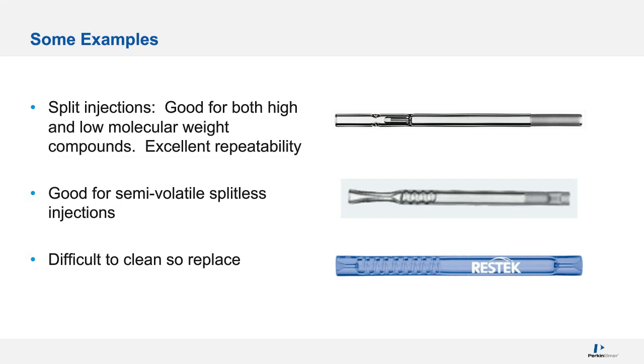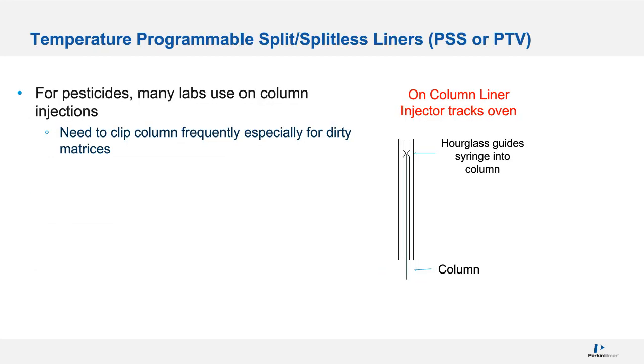There's many of them. The other thing some folks do, and this is a little risky because of activity, some folks use on-column injections when they run pesticides, but then if you have very dirty samples, you're putting that non-volatile junk right onto the analytical column. Now, column vendors sell integrated guard columns, which are really, really cool because then you don't have to worry about having a butt connection where that's a source of a leak. But if it's drinking water running 508 or 525, those samples are clean, and we wouldn't have to clip as frequently as if we're doing dirty matrices.